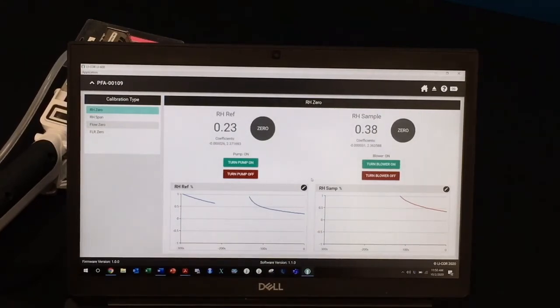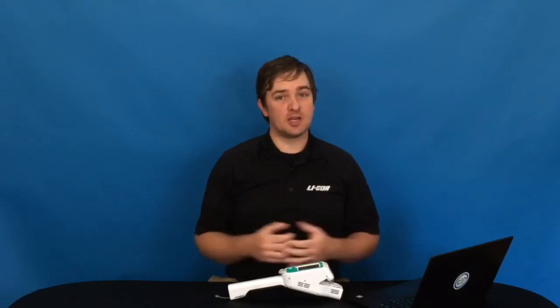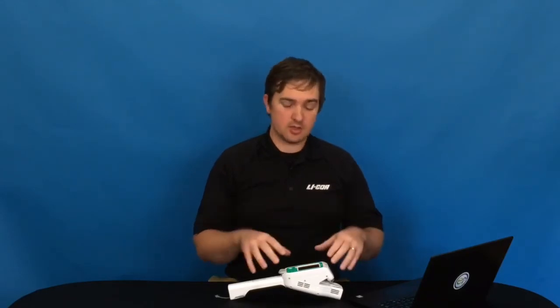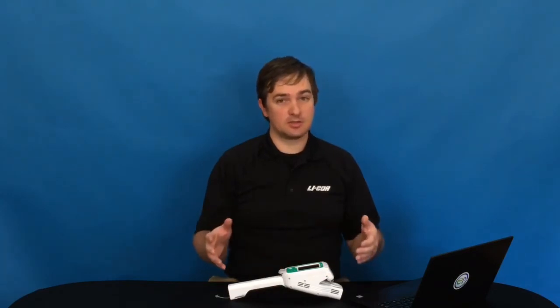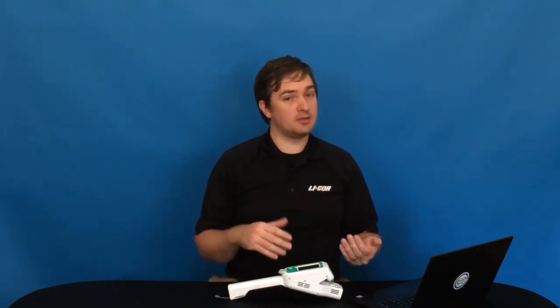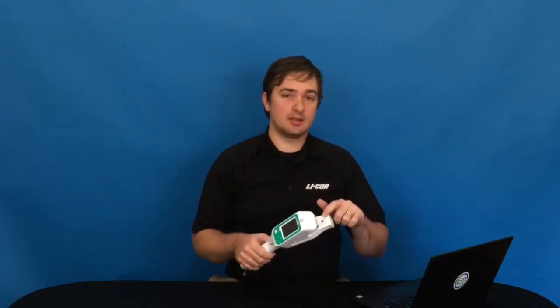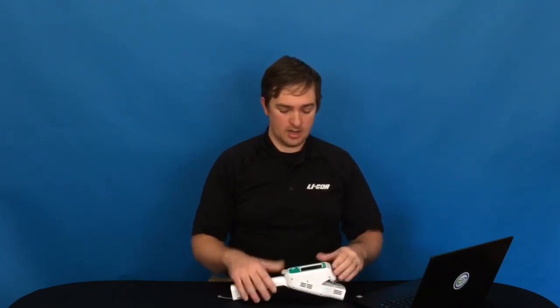Once you've performed this relative humidity 0 calibration, you can exit this menu, put the instrument back together, including putting the buffer beads back into the instrument and putting the shells back on before making measurements. So that is how you do a calibration. Once you're finished, make sure that you put the instrument back together completely as it was, including replacing the buffer beads if you've taken those out, replacing the leaf clamp if you've taken that out, and putting the shells back on the sides of the instrument. Now you're ready to go make measurements.